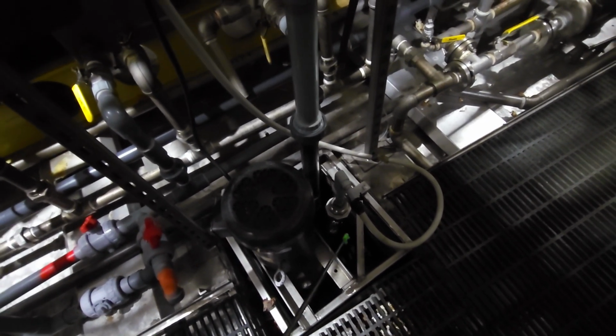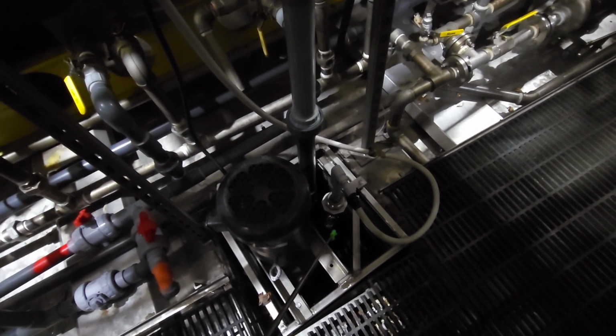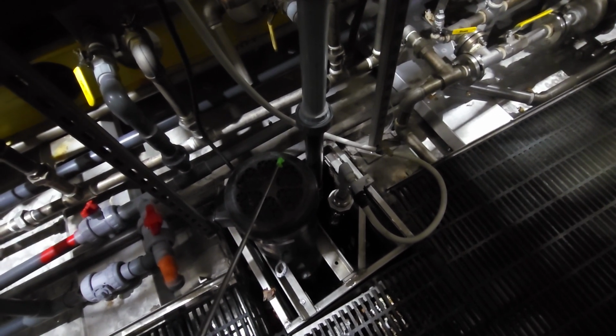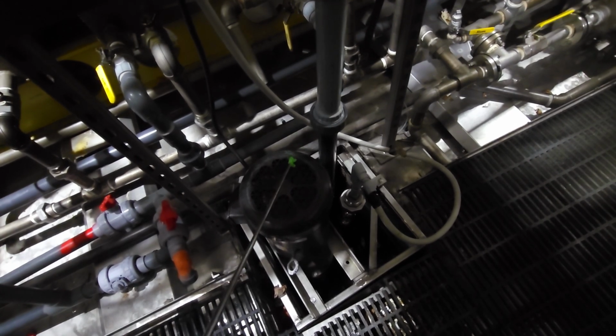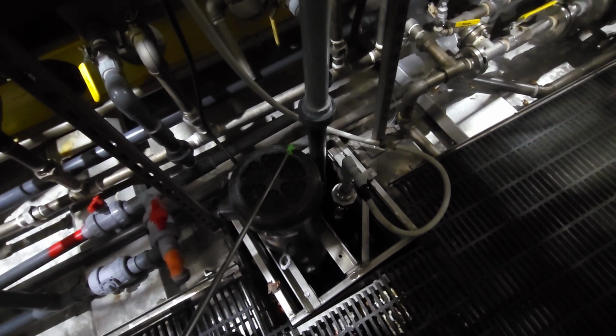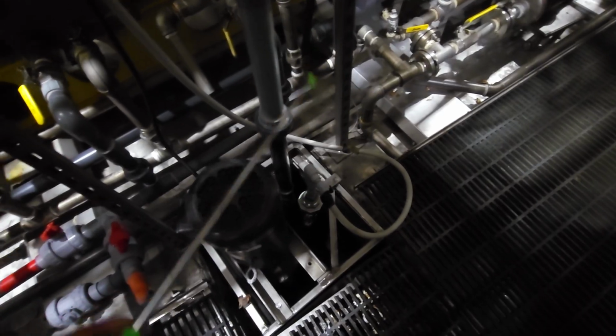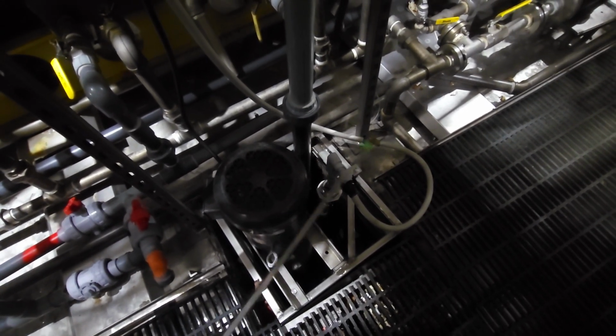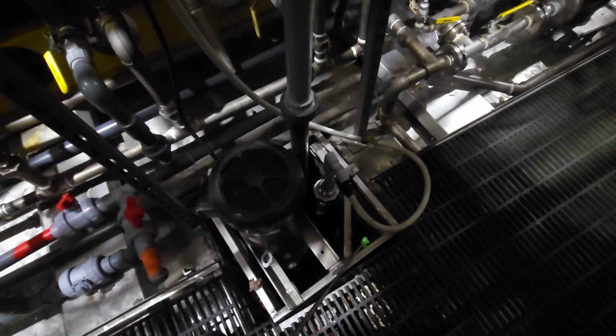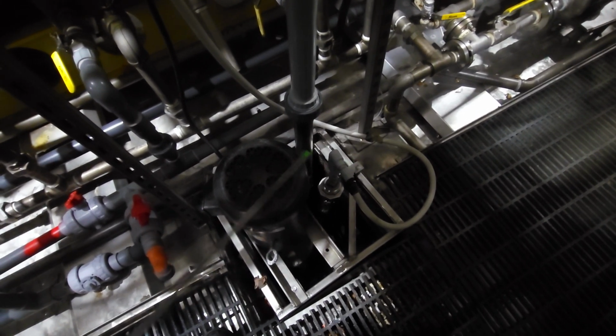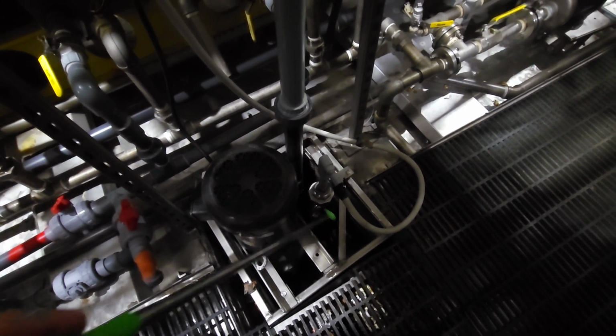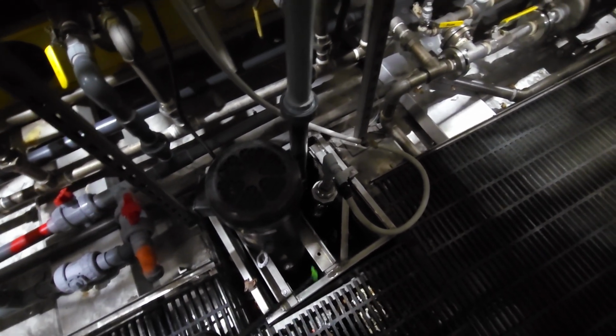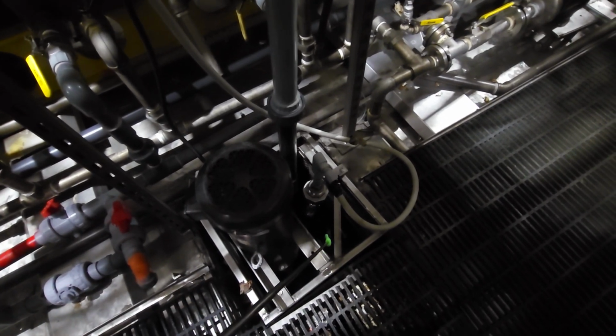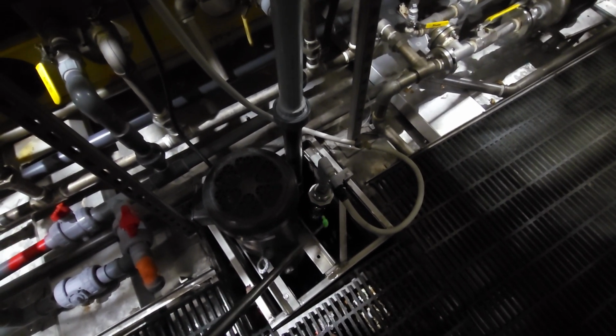So the main thing you'll run into is that middle ball will just be turning the pump on and off real quick. When it does it like that, what usually happens, it'll hit the overload. It'll blow the overload. So a lot of times just come back and kick the float. If that don't work and you cleaned it, well, in that situation it's time to change it. Ain't no reason to play with it. You need to be careful. These floats aren't grounded except for when they're mounted. If they're not mounted, they're not grounded. So if one of those is leaking inside, the voltage is leaking, and you pick that up and you touch ground, you're going to feel it. It's 110.